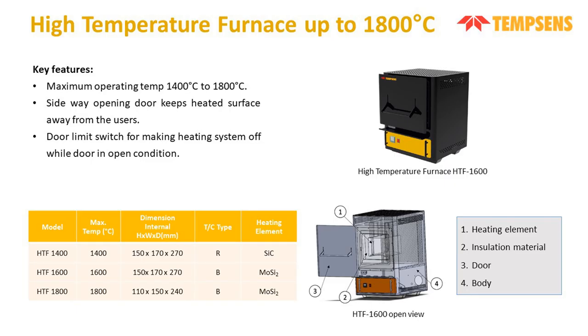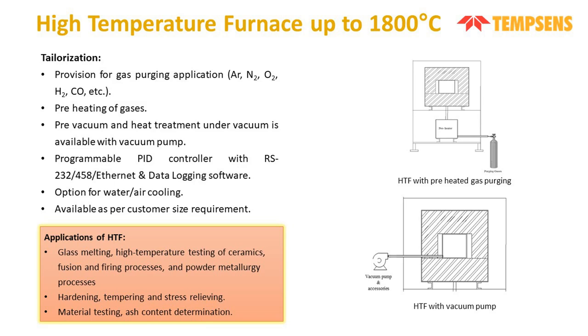Now we come to the HTF, which is the high temperature furnace. In HTF we have furnaces up to 1800 degrees Celsius. It is the same as a muffle furnace, but the chamber size is much bigger. We have a side opening door, and the high temperature furnace is basically of three types. We have divided the furnaces on the factors of dimension and the maximum temperature they can reach. So there are basically three furnaces: 1400 degrees Celsius, 1600 degrees Celsius, and 1800 degrees Celsius. For different furnaces and different models, we have used different types of thermocouple, and accordingly the heating element according to the temperature.